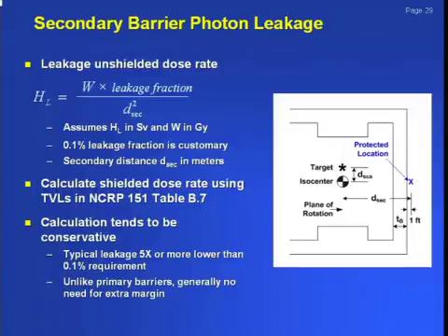So I know we have some safety factors in here. Again, I think a lot of it is because we have to assume that we are using a 40-wide field. If you can pass a safety survey with a 40-wide field, you know you are going to be safe when you actually operate the machine, because you are going to be treating patients with a much smaller field than that.